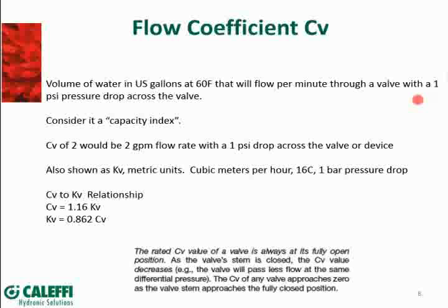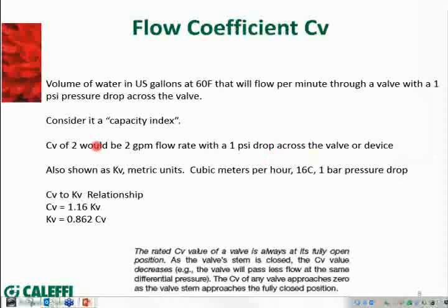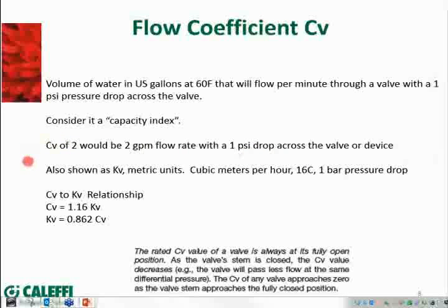A CV of two means that a two-gallon-per-minute flow through a valve or device would have a one PSI pressure drop. If you had a differential pressure gauge that could measure the pressure on the inlet and outlet side, at this flow rate of two GPM you would have a one PSI drop, and that's how they come up with the CV number.